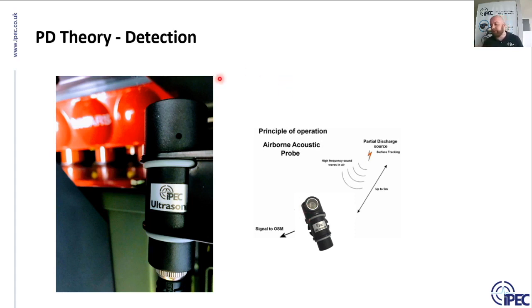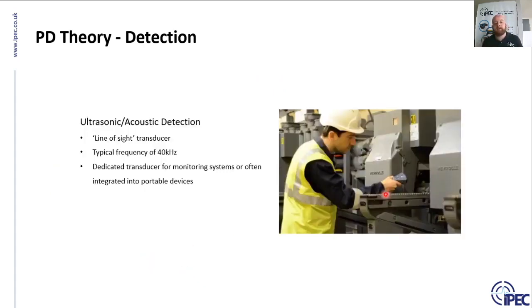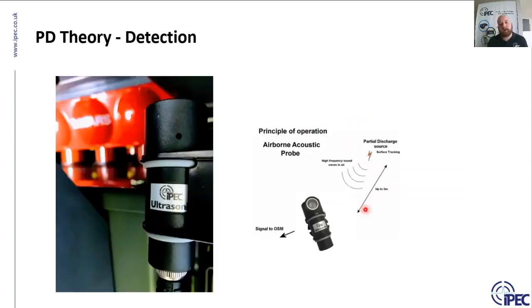So we have sensors for permanent monitoring systems, and we also have sensors that we build into handheld devices, like in this next image. So built into handheld devices to pick up the PD. Now, modern switchgear tends to be more enclosed, so the locations where we can apply our ultrasonic sensors can be more limited. However, where they can be applied, it's very, very sensitive.